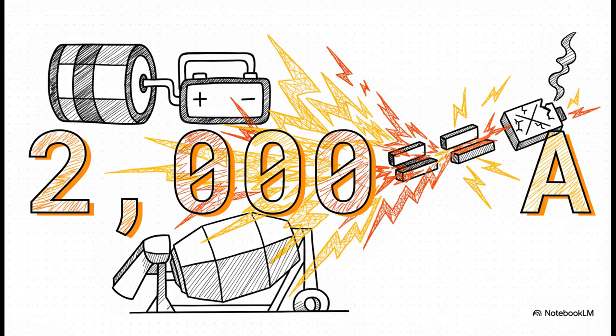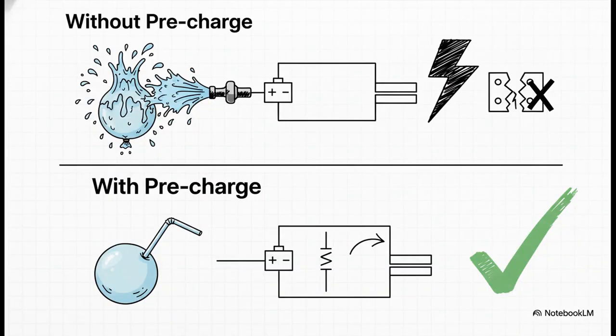It's brilliant. But there's another hidden danger lurking in this system. The motor controllers have these massive capacitors inside, and if you were to just connect the battery directly, those empty capacitors would look like a dead short to the battery. For just a split second, you'd get a surge of current of maybe 2,000 amps or more. That's enough to literally weld the main power relays shut and cause a catastrophic failure. So how do we stop that massive surge? The solution is a really elegant pre-charge circuit. Before closing the main power relays, the system first closes a smaller relay that sends all that power through a simple resistor. This resistor gently fills up the capacitors. It's exactly like filling a water balloon with a thin straw instead of a fire hose. Once the voltage is stable, the main relays close safely, and the system is ready for work.